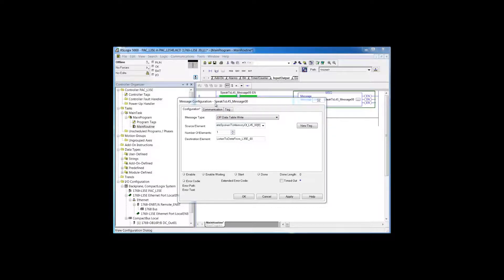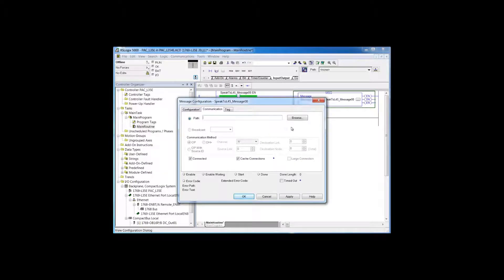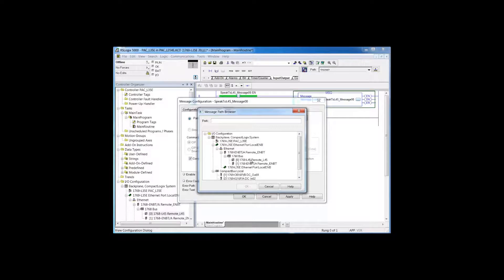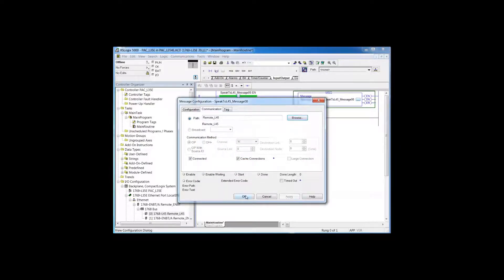The other thing we have to do is go to the communications tab and browse to find our destination. You could type in the path manually. One of the beauties of the Logix engine is that once we've added the other controller into the IO configuration, we can simply browse to find it. We want to reach the L45 from our L35E project by way of Ethernet. So we browse: L35E → Ethernet → ENBT → 1768 bus → L45. We click there, the name populates, and the path is defined. Apply and OK.